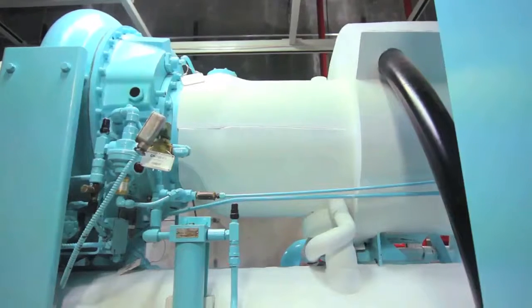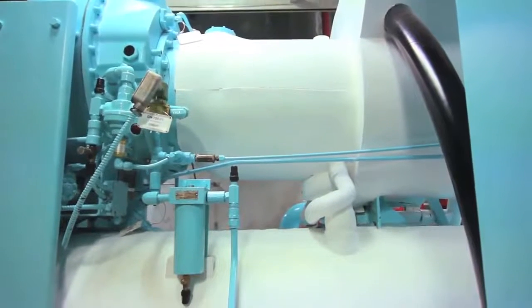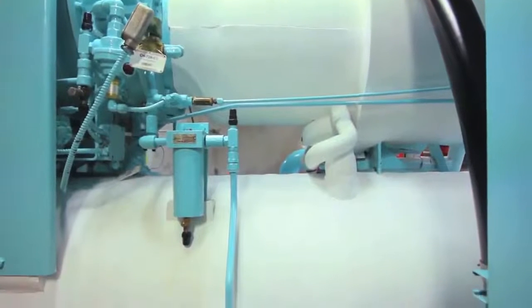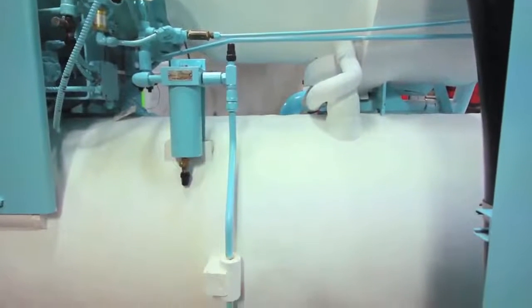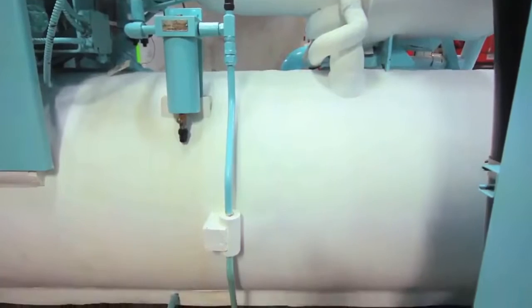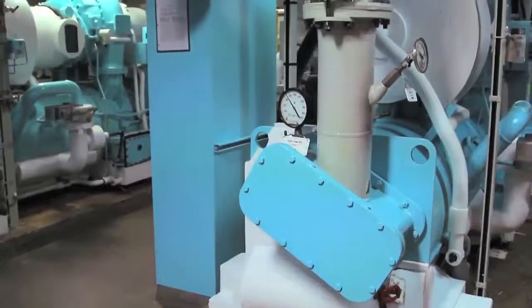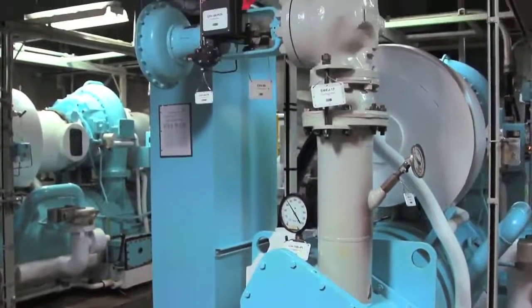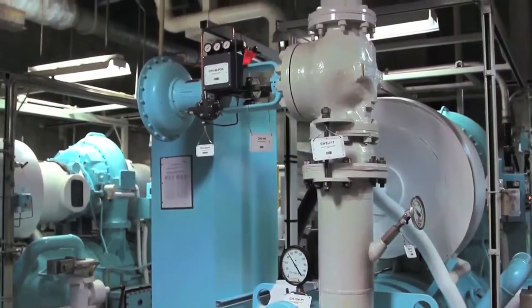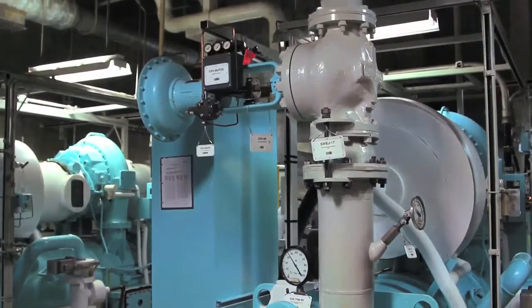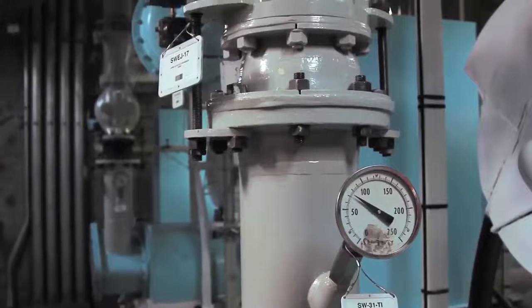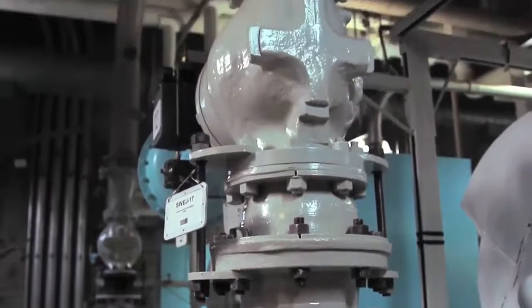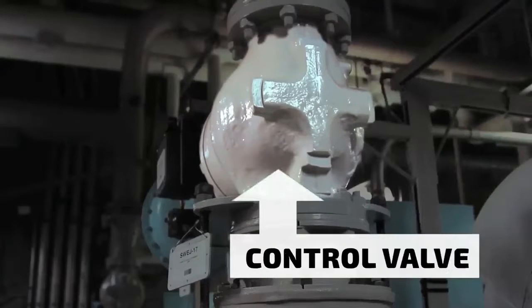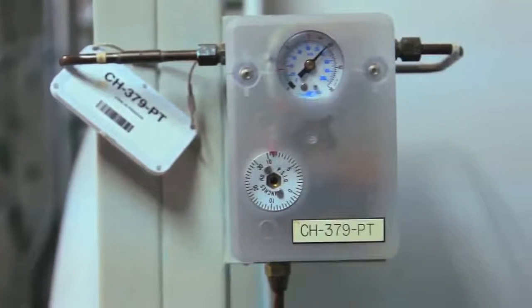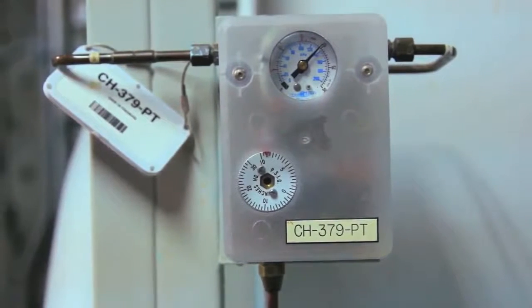Heat exchanger tubes also have non-destructive examinations, referred to as NDE, performed on a periodic basis per the plant's preventive maintenance program. Service water supplies the secondary cooling water for the condenser, passes it through the condenser tubes and back to the SW system. This condenser has a control valve on the discharge side. This valve is a pneumatic valve which regulates the discharge volume of the condenser. This ensures we extract the proper amount of heat.